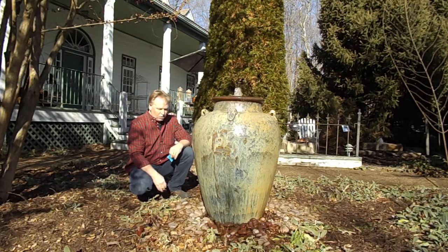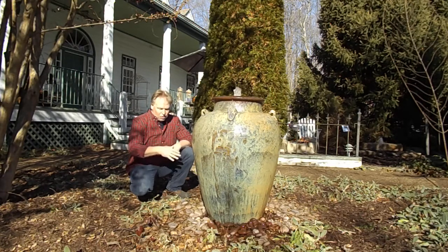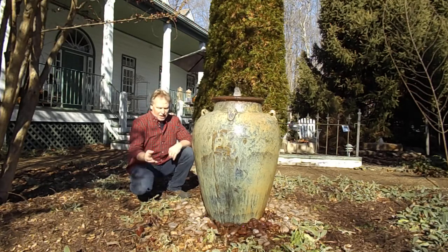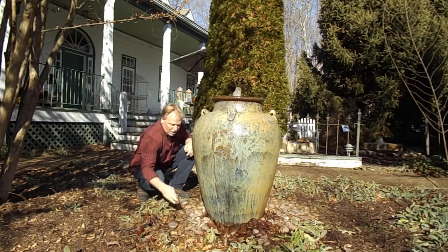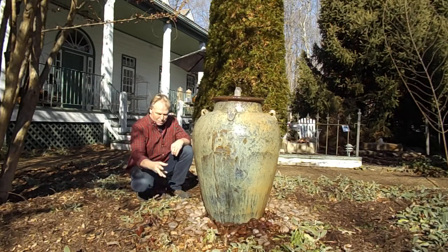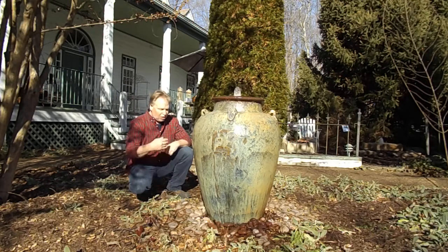Basin cleaning — if you wanted to, you could clean this basin. This basin's never been cleaned. It's been here 15 years, directly under a crepe myrtle tree — a messy tree that drops blooms, leaves, and seeds all the time. It's probably got a couple inches of sludge in the bottom after 15 years, but that sludge is settled so it really doesn't become an issue. In those 15 years, the two hours of maintenance has been cleaning the intake on the pump. That debris will finally work its way through the screen, so I pull the rocks away, lift out the panel for pump access, grab the debris, and throw it out. You have to do that about once a year.